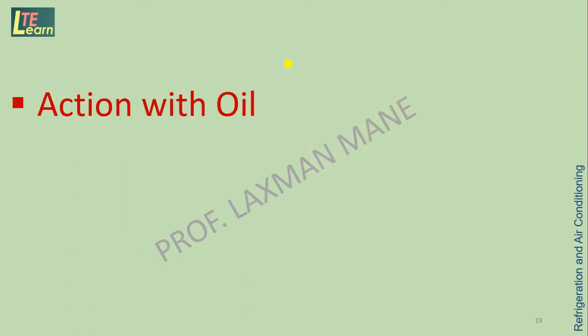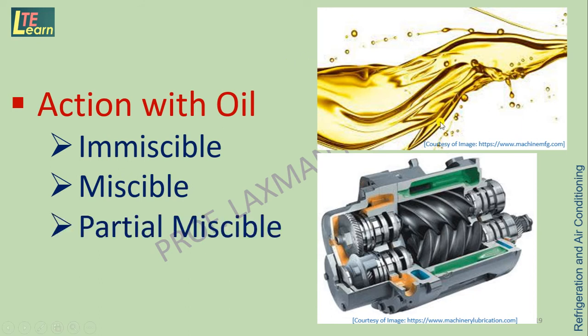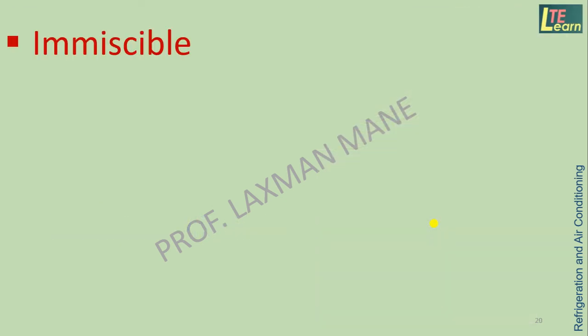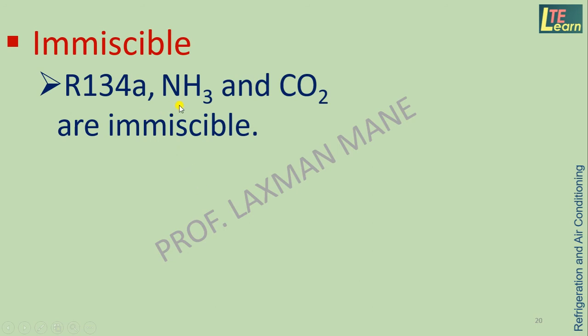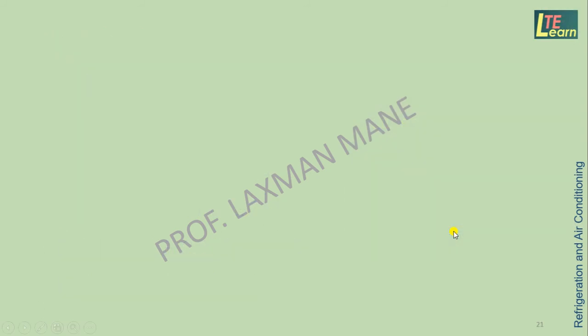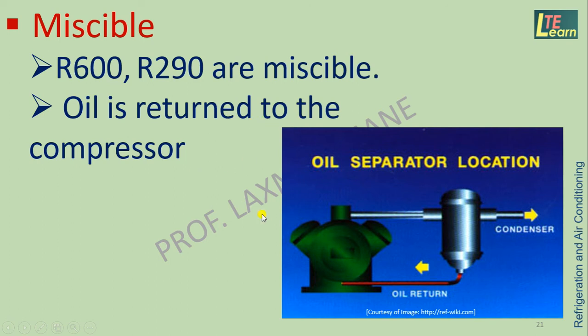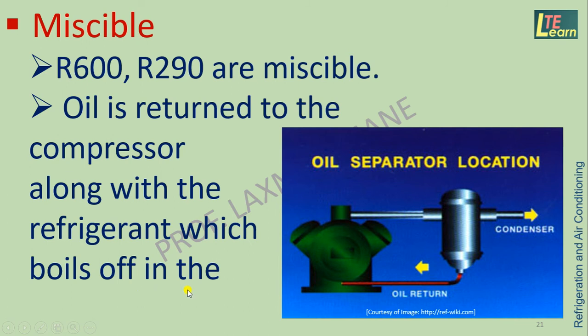The action of refrigerant with oil falls into three categories: immiscible, miscible, and partially miscible. Oil used in a compressor for lubrication is used along with refrigerant. For immiscible refrigerants — R134A, ammonia, and carbon dioxide — an oil separator is installed in the discharge line after the compressor to separate the lubricant oil and prevent it from passing to the condenser. Miscible refrigerants such as R600 (butane) and R290 (propane) allow oil to return to the compressor along with refrigerant, which boils off in the evaporator.